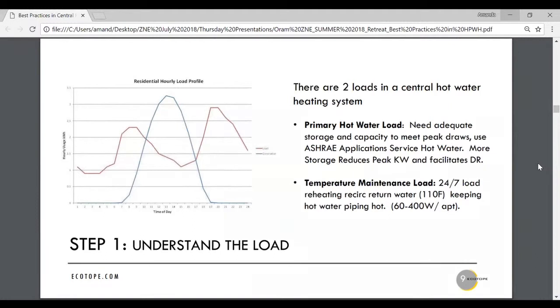The range is 60 to 400 watts an apartment. So take your number of units times a range of 60 to 400, purely a function of insulation levels on your piping, how you're clamping these, how you're insulating. Remember, this is an entire hot loop - it wants to lose heat, and you're trying to contain it.